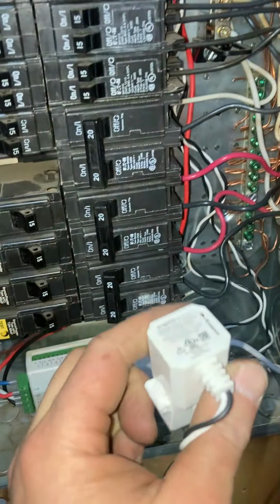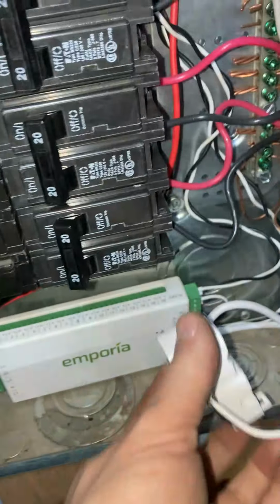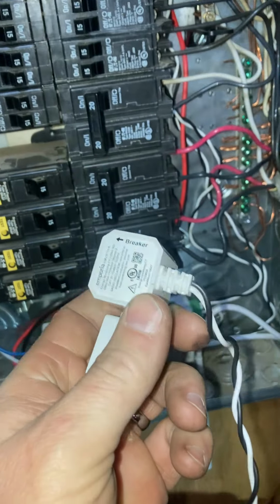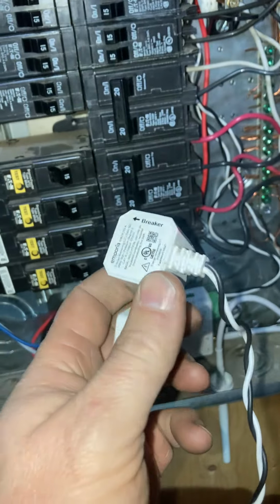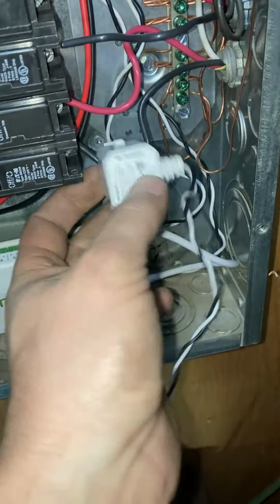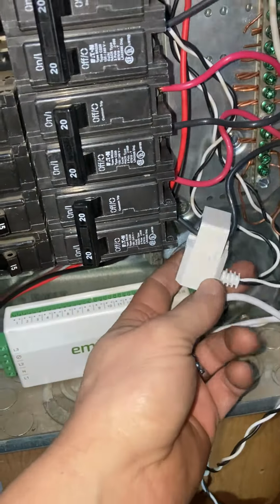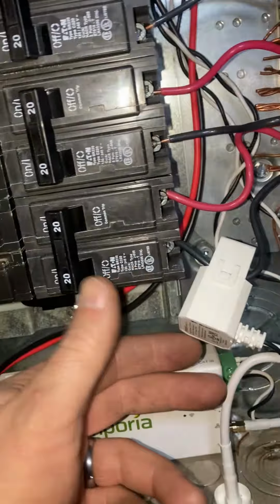So we hook these up very much the same way, breaker pointing that way. If you have something like a water heater, you can get away with using one of these, and then in the app, you put a multiplier of 2 on it. So in this case, we're going to click that onto one of the two, on that tandem breaker right there.